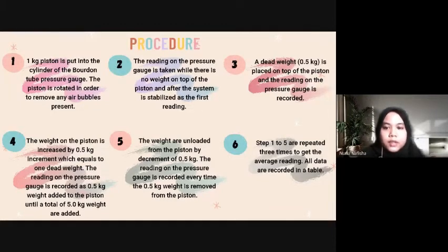Next, a dead weight, which is 0.5 kilogram, is placed on top of the piston and the reading on the pressure gauge is recorded. Fourth step, the weight on the piston is increased by 0.5 kilogram increments, which equals 1 dead weight. The reading on the pressure gauge is recorded as each 0.5 kilogram weight is added to the piston until a total of 5 kilograms of weight is added.